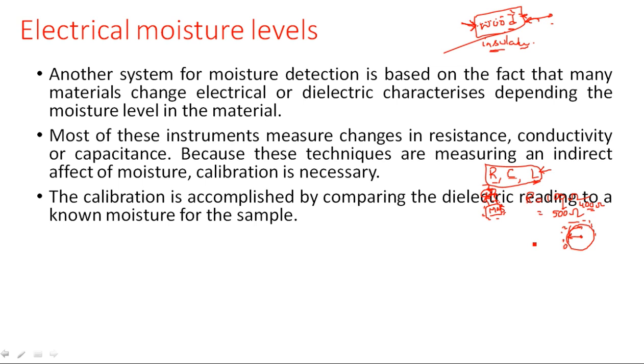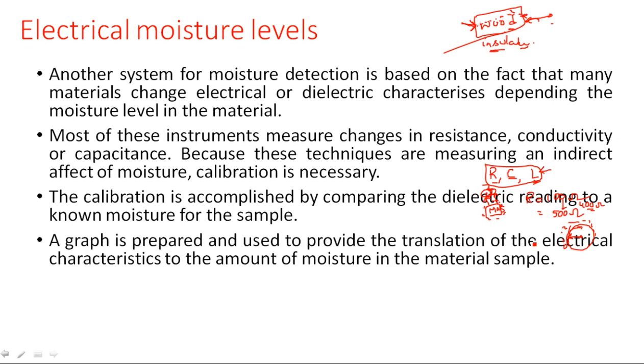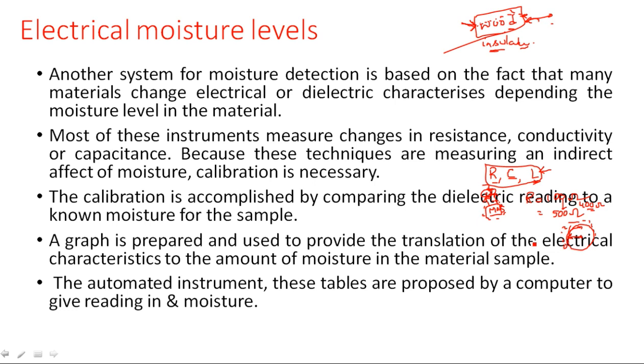Calibration is accomplished by comparing the dielectric reading to a known moisture level for the sample. The unknown measurement is compared with the known measurement, and a scale is designed accordingly before the product is developed. A graph is prepared and used to provide the translation of electrical characteristics to the amount of moisture in the material. Automated instruments use these tables, proposed by a computer, to give readings in moisture.